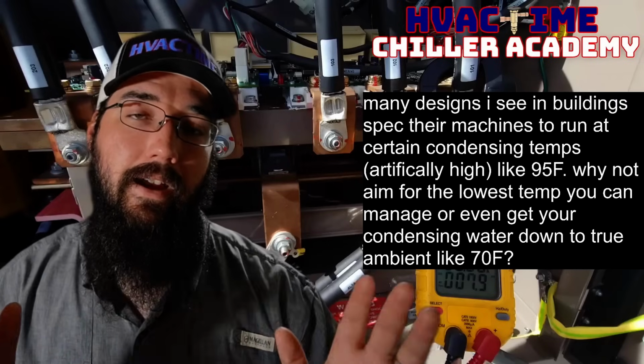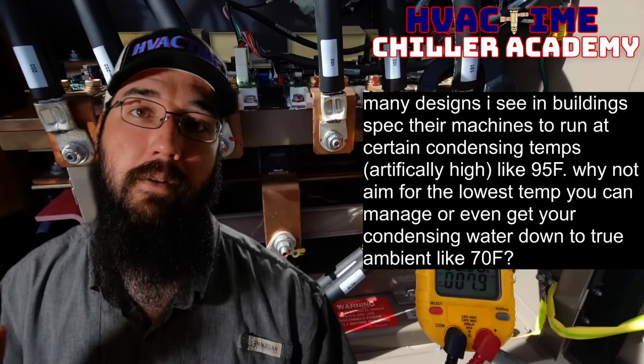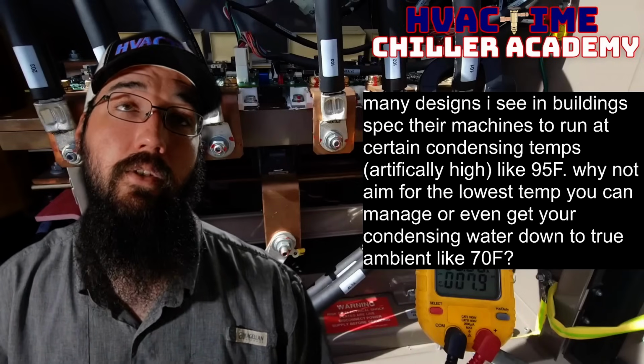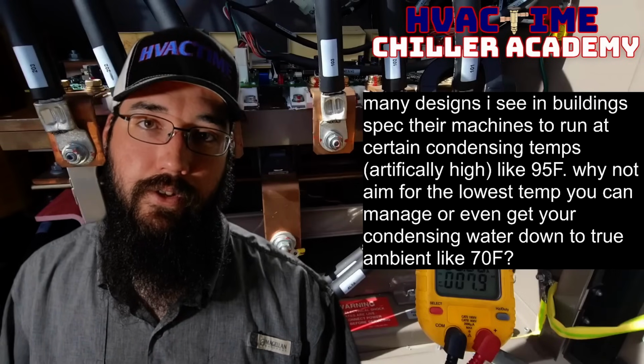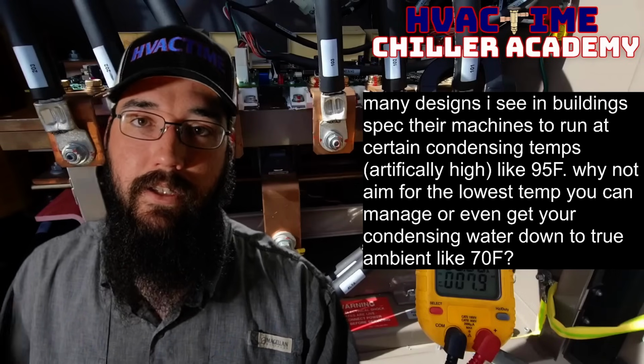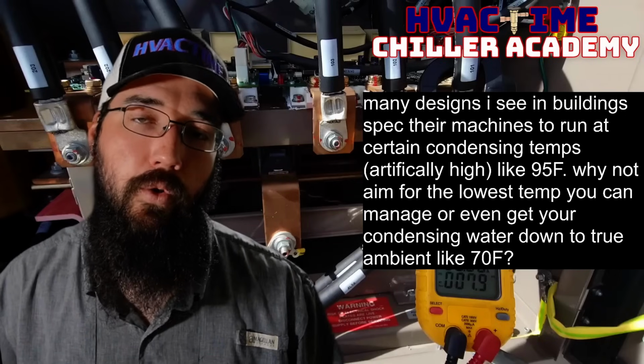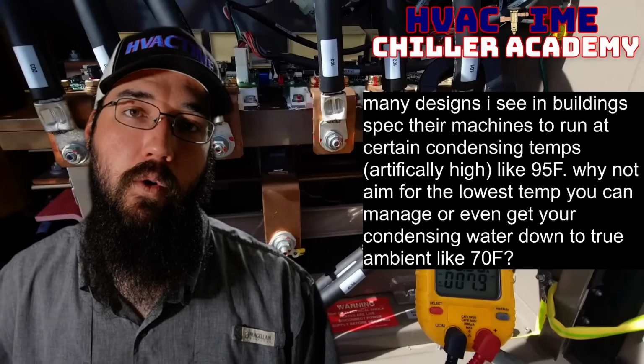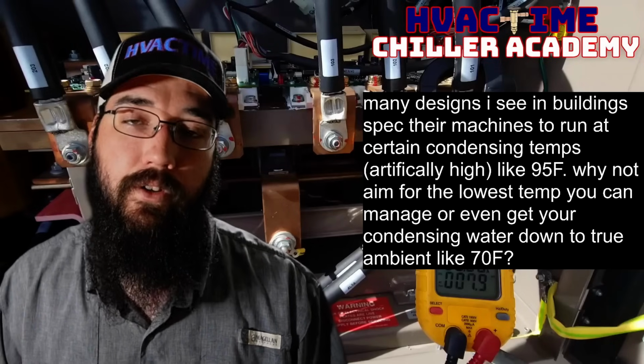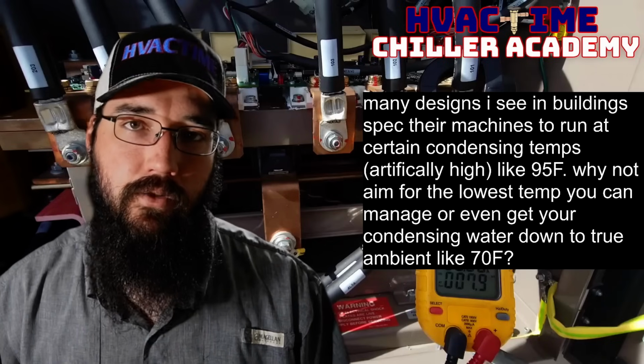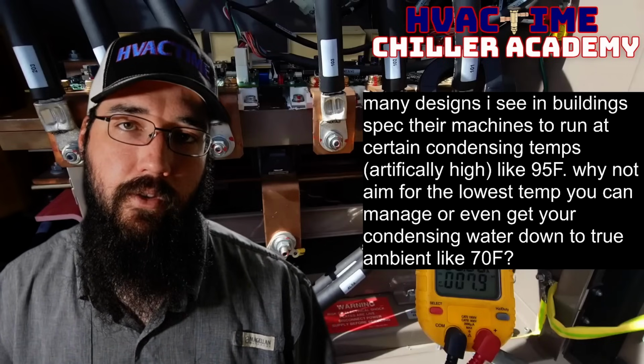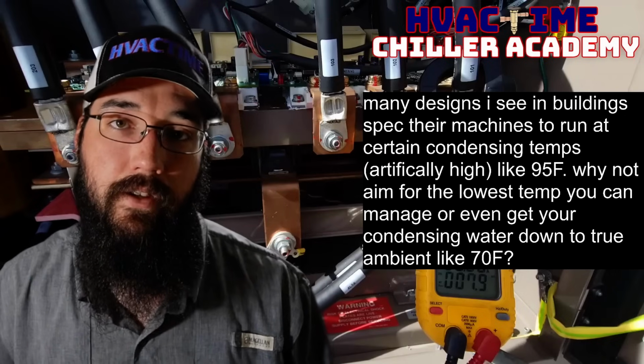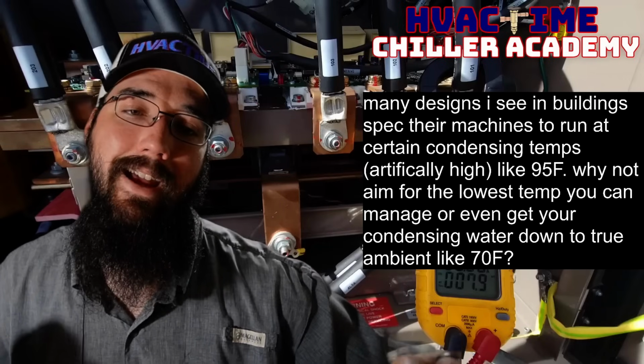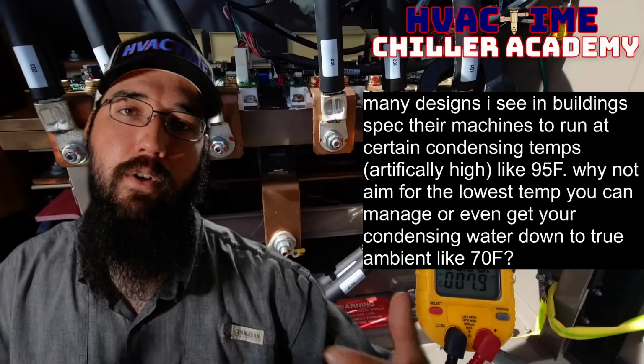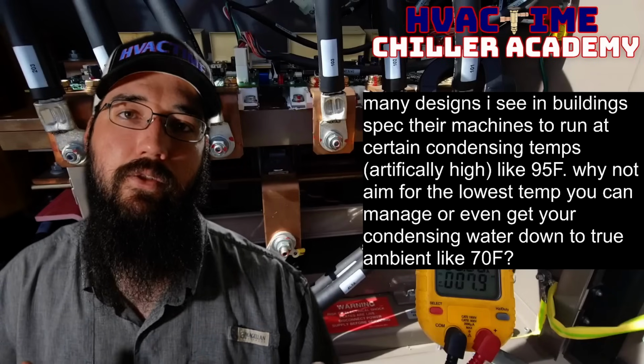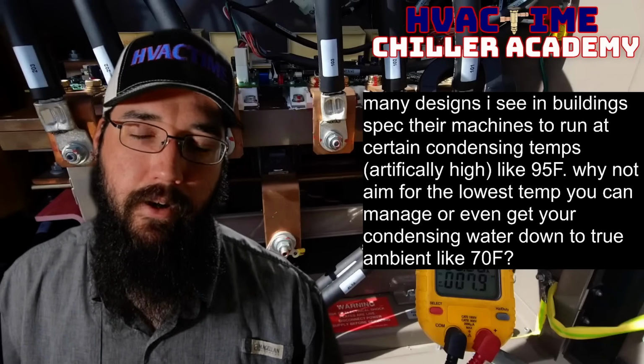Okay. Now, I take that a step further to where we need to set some minimums and maximums based off of our chiller. So with a lot of chillers like your RTHD or a CVH, CDH, those cannot operate with cold condenser water. They need that warmer water to maintain proper oil return, because if we drop that condenser water too low, the eductor system can't recover the oil back properly, because we're using hot gas off the condenser to feed the eductor circuit. So if we do not have enough velocity on that hot gas, we cannot properly create the Venturi effect, the siphoning effect, to draw that oil-laden refrigerant back off of our evaporators, which then allows it to stack up.